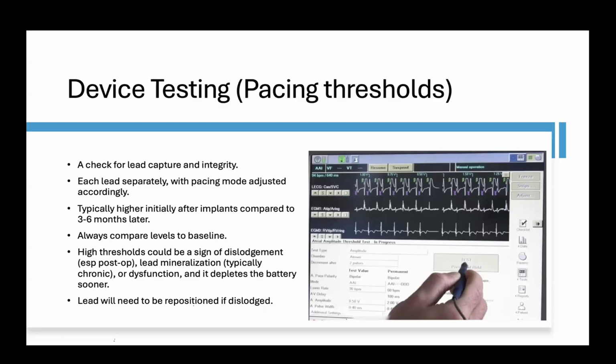We always have, as I mentioned, to compare the levels we find to the baseline levels, because if the patient has a high threshold to start with before the surgery, high thresholds after the surgery within the same range is not a big issue. It does tell that maybe the lead is getting older. There's some chronic issues with the lead rather than a new issue or an acute issue that happened during the surgery or before or after the surgery. And high thresholds could be a sign of lead dislodgement in general, especially after procedures or surgeries. Chronic high pacing threshold levels could be due to lead mineralization or dysfunction.